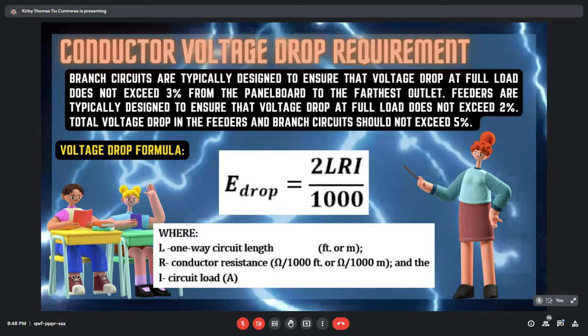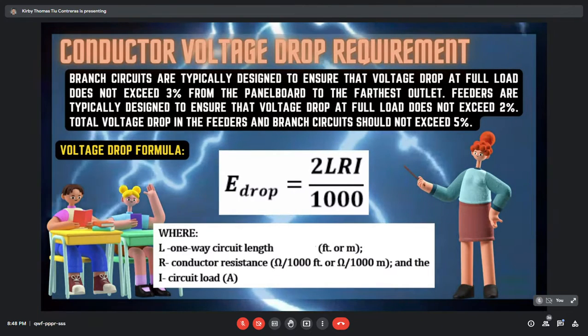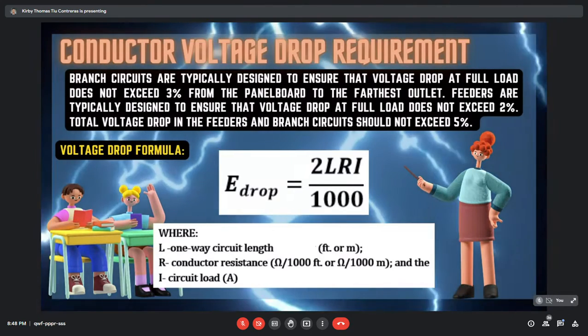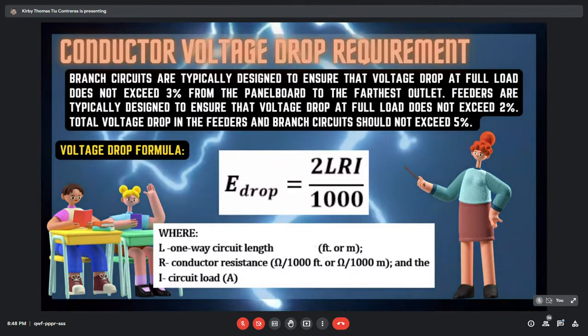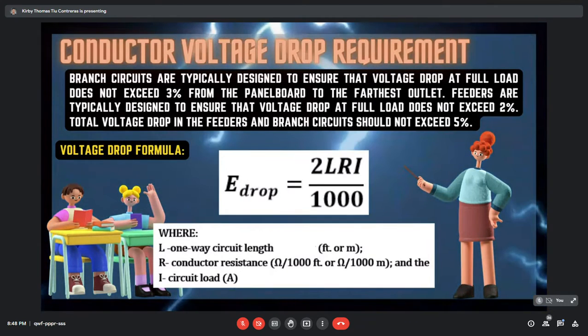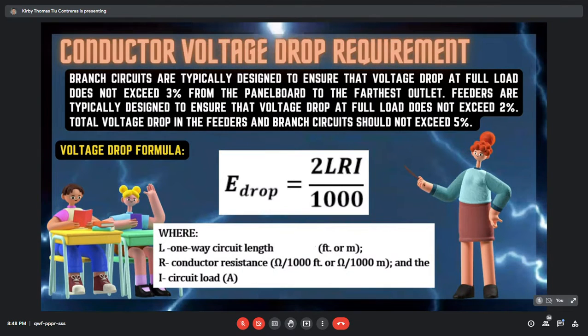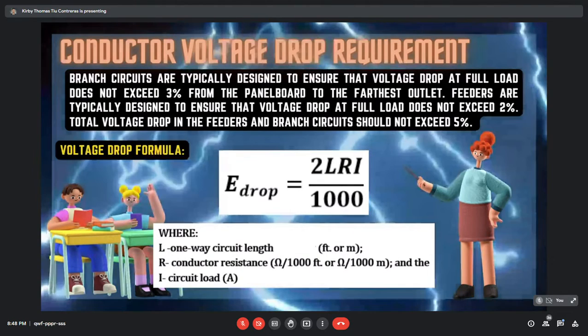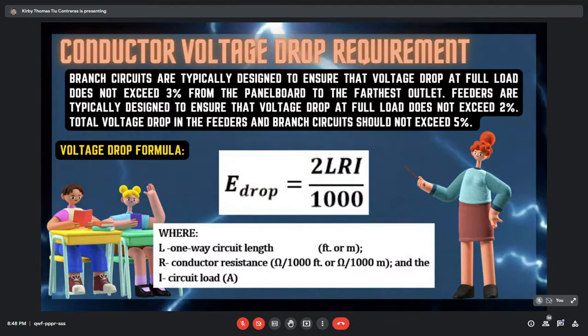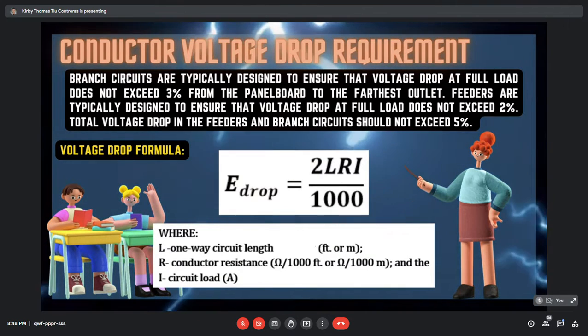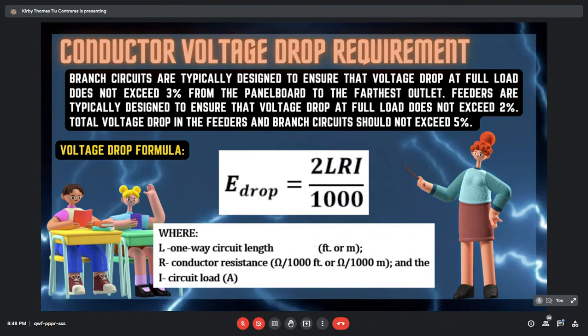So, in addition to capacity requirements, branch circuits and feeders should be analyzed for voltage drop because of the adverse effect it can have on the performance and operating life of appliances and equipment. So, branch circuits are typically designed to ensure that voltage drop at full load does not exceed 3% from the panel board to the farthest outlet. Feeders are typically designed to ensure that the voltage drop at full load does not exceed 2%. So the total voltage drop in the feeders and the branch circuit should not exceed 5%.